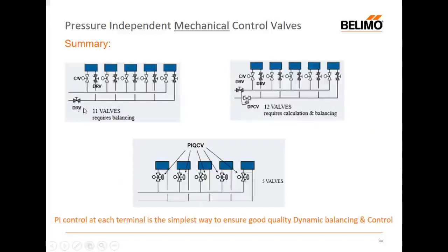And then the branch that these valves are located in has to be balanced against the other branches, so I'll need a bigger DRV on the branch. And maybe if there are multiple risers, I'll want to balance the risers as well. So in this example, to achieve a balanced and reasonable control, we're going to need 11 valves. We're going to suffer interactivity because the control valve is the only form of dynamic control in this branch. So we know that we're going to get overflows and underflows because interactivity brings that about.